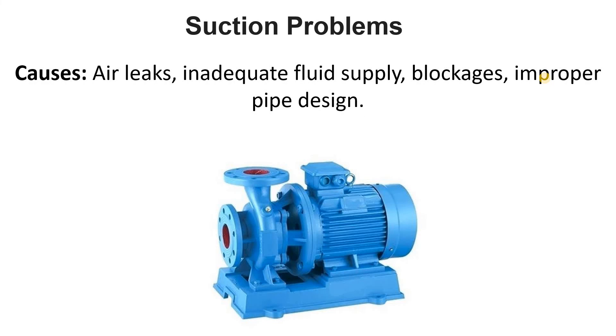The next defect is suction problems, which are somewhat similar to cavitation. Please watch the centrifugal pump playlist for more detailed coverage. Suction problems can include air leakage, inadequate fluid supply, blockages, and improper pipe design. Cavitation and vibration can also be associated with suction problems, as well as leakage in the suction line — these must always be considered.